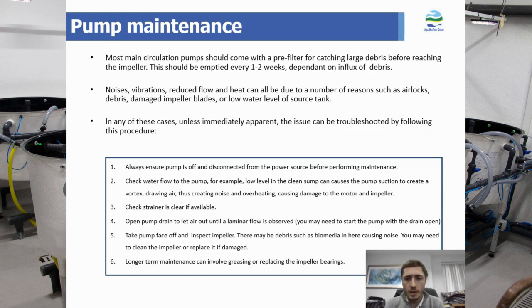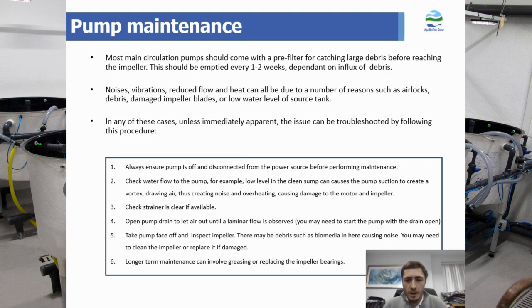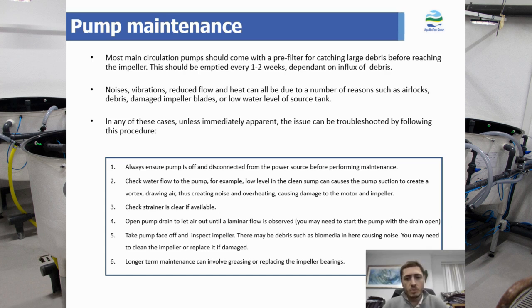As with any electrical component, ensure it's disconnected from the power source before performing any maintenance. Check that the water level I mentioned, and address that elsewhere within the system if that is the problem. Check that the pre-filter or the strainer is clear of any debris. If you're still having issues, some pumps will have a drain point on them to allow for removing any air or filling the pump. Some pumps aren't self-priming and will need to be filled or just to have the air released before they work. So if you have this on your pump, open it up and wait until you see water coming out steadily. If you're still having trouble, you can inspect the impeller by taking off the face of the pump. Longer term maintenance — around two-year maintenance — would be to properly open it up, grease any gears, and maybe replace some of the impeller bearings.